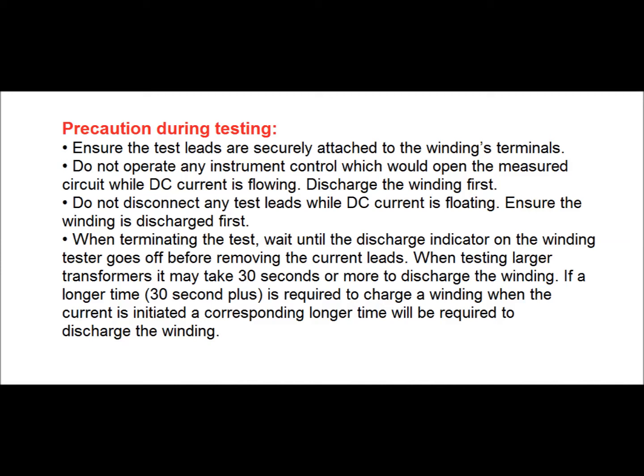We have to ensure that we do not disconnect any test lead while DC current is flowing. Ensure the winding is discharged first. When terminating the test, we have to first discharge the DC current, as shown in the winding resistance tester, until the current goes to the zero value. When testing a larger transformer, it may take 30 seconds or more to discharge the winding.